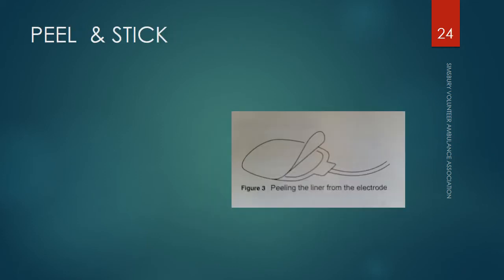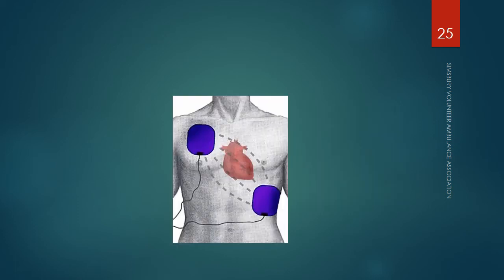The way that you've opened up the package, you've pulled the pads out, and the way you want to remove the backing is from where the electrode is. There should be a little tab, and you can peel the pad paper back. Okay, you don't want to peel from any other direction because you're going to have trouble finding where the little lip is. So you want to start where the electrode meets the pad, and you'll notice that there's a piece of the backing that's very easy to lift, and then just peel it straight back. And then you're going to stick it to the patient.